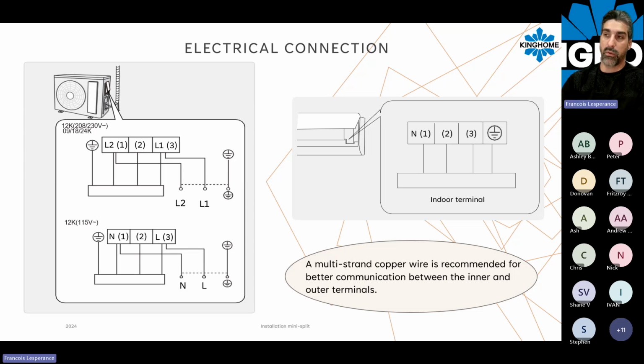To check very quickly the proper voltage for this kind of problem, make sure you unplug the wire on terminals 1 and 2, and with your multimeter, measure whether you have 56 volts DC directly on the board from the outdoor unit. If you have 56 volts DC directly on the screw or the pin here on the board, that means you have a good board, and then you must look at the connection on your wire. Make sure you don't have any wires to ground, or maybe bad continuity in your wire.